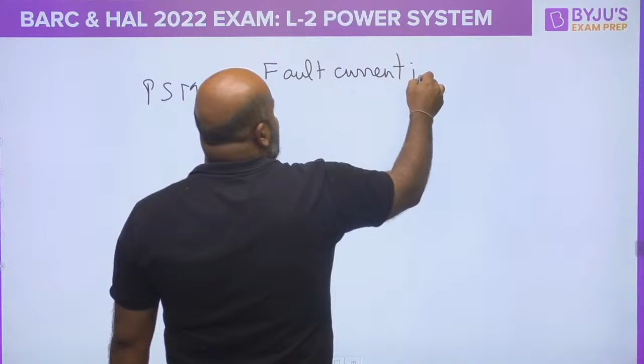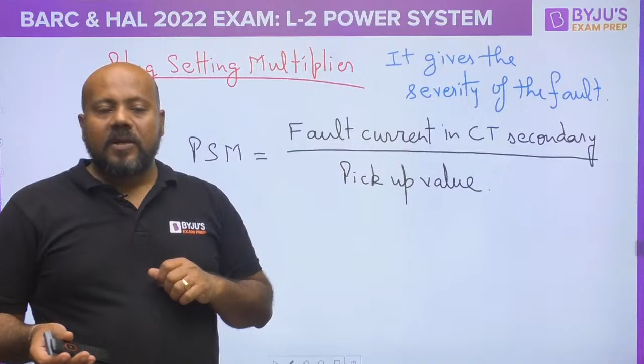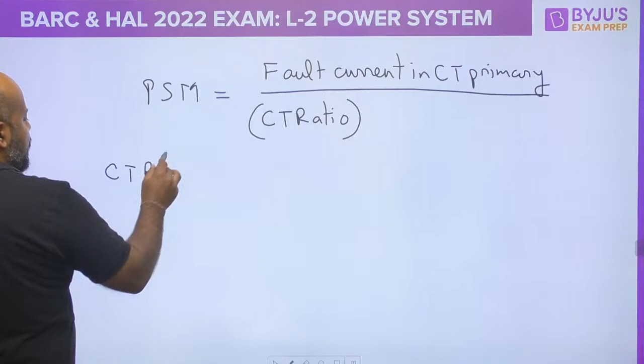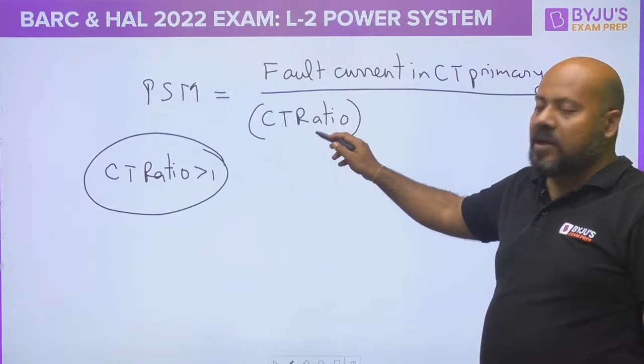But the problem is, when he gives you the question in the examination, he will not directly give you this current value. He will actually give you the value of the fault current in the primary, that is the fault current in the line. Now you can very well understand that if I have to write, listen very carefully, the fault current in CT primary here, and what you actually want is the fault current in the CT secondary, what is going to be a bigger value? Fault current in the CT secondary or fault current in the CT primary? Definitely the fault current in CT primary is going to be a larger value.